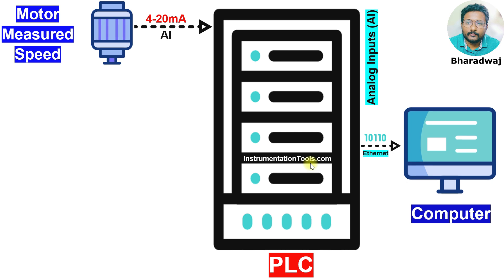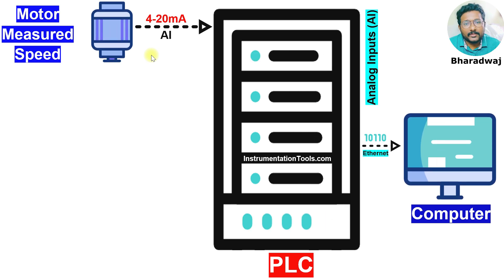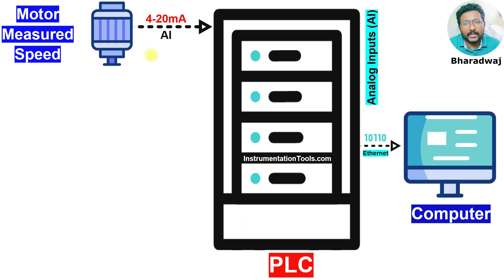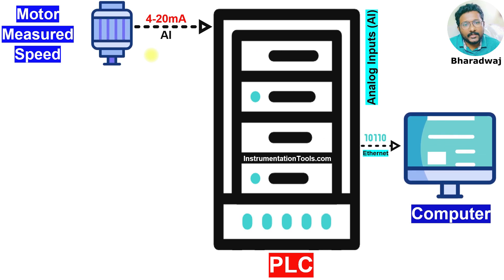You will receive the signal in 4 to 20 mA — it is AI, that means analog input to the PLC. Also, some other parameters related to the motor are power consumption, current value, voltage value, frequency value, etc. You can take these values from electrical feeders or variable frequency drives.